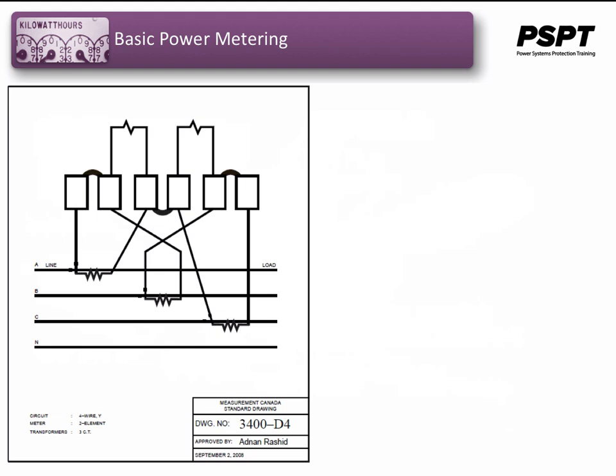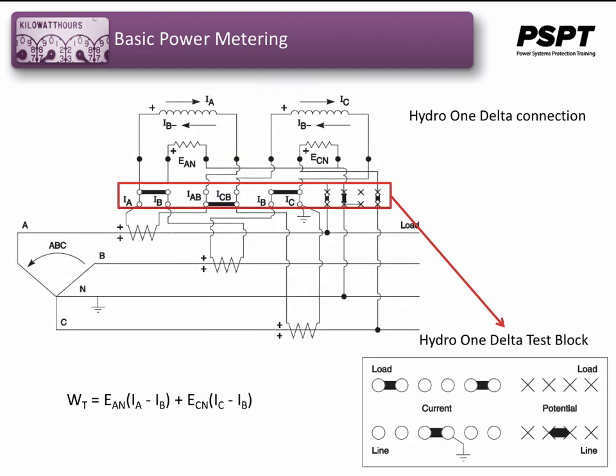Once the flexi-test switches are mounted, they are wired to a standard, which is also found on the Measurement Canada standard connections. This figure shows a typical installation of a 2-element meter with the Hydro One Delta connection. Notice the indicated current flow through the CT and meter coil and the labeled currents at the test block. Also note that the neutral potential is shown having a solid or dummy fuse. This is the required connection.